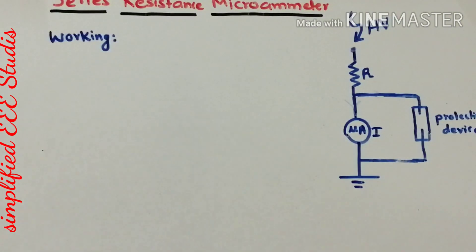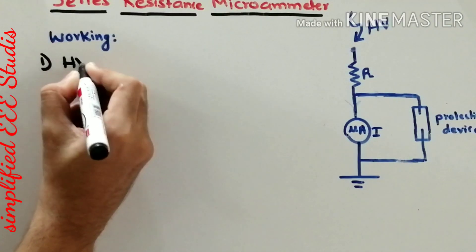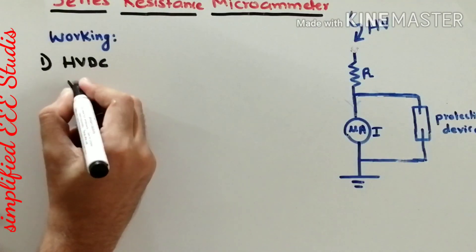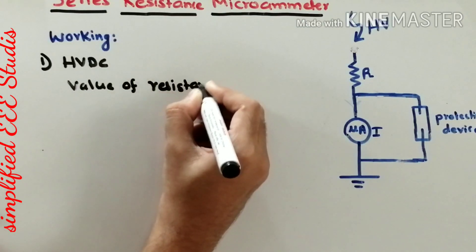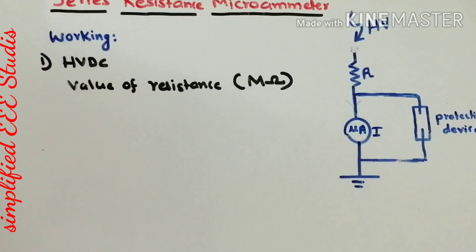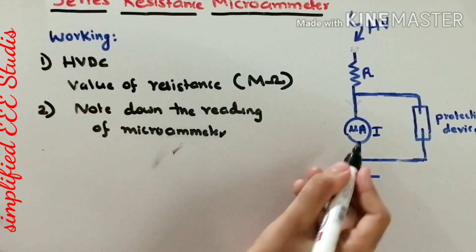Now let me explain the working of the series resistance microammeter. The goal is to measure HVDC — high voltage DC will be applied. You need to note down the value of resistance, which is in the range of mega ohms. You connect a microammeter in series with the resistance. Depending on the applied high voltage DC, you will get a reading on the microammeter.